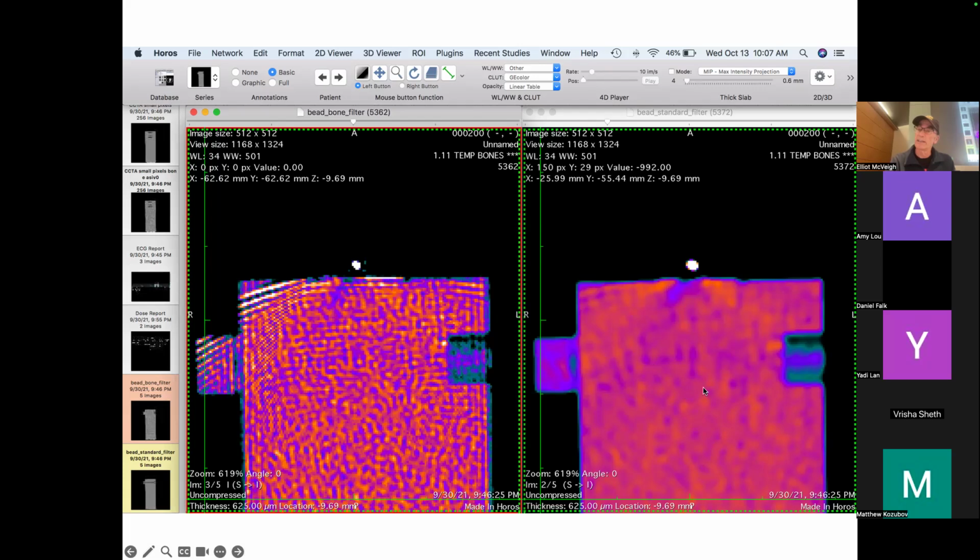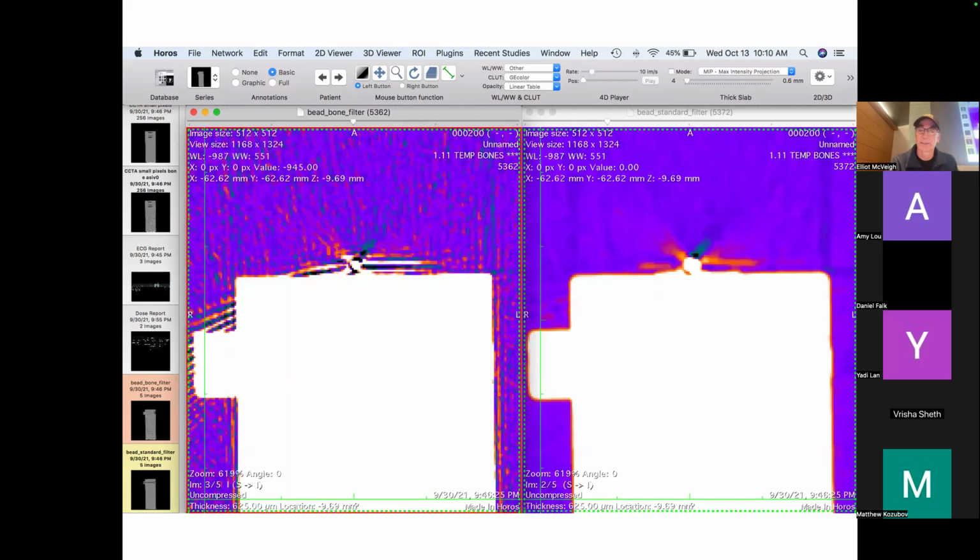When we, as opposed to using the Ram-Lak filter or the pure ramp, roll it down like that filter I just showed you, it reduces the noise considerably, and it reduces these artifacts because you can't visualize those spatial frequencies after you filter with this. So it makes the image look smoother, much more well-behaved.